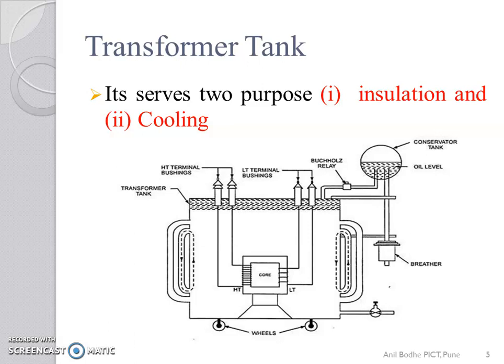Transformer tank is used only for big size or big capacity transformer. It is not used for small size transformer. The whole transformer assembly is placed in a fabricated sheet metal tank and immersed in the oil, which serves both the purpose of providing insulation and cooling. The heat generated in the winding and the core of the transformer is carried by the oil to the external surface of the tank, and the cooling tubes are provided to increase the surface area of the tank for more effective cooling.